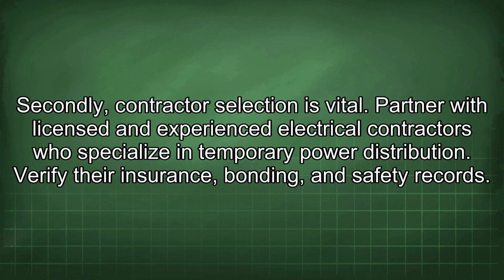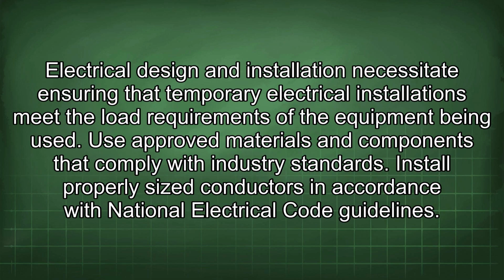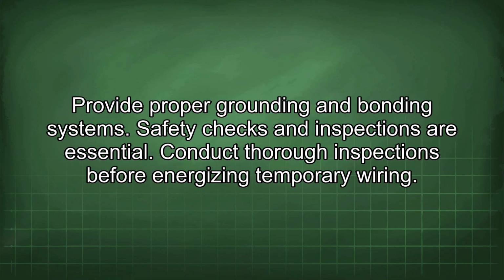Secondly, contractor selection is vital. Partner with licensed and experienced electrical contractors who specialize in temporary power distribution. Verify their insurance, bonding, and safety records. The electrical design and installation necessitate ensuring that temporary electrical installations meet the load requirements of the equipment being used. Use approved materials and components that comply with industry standards. Install properly sized conductors in accordance with National Electrical Code guidelines. Provide proper grounding and bonding systems.